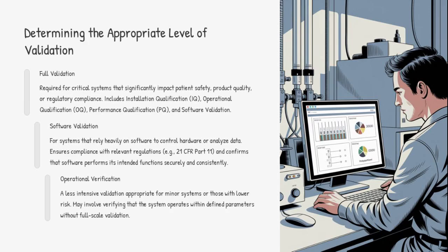Determining the appropriate level of validation is required for systems that significantly impact patient safety, product quality, or regulatory compliance. Full validation includes installation qualification, operational qualification, performance qualification, and software validation. For systems relying on software to control or analyze data, software validation ensures compliance with relevant regulations. Operational verification is a less intensive validation appropriate for minor systems or those with lower risk.